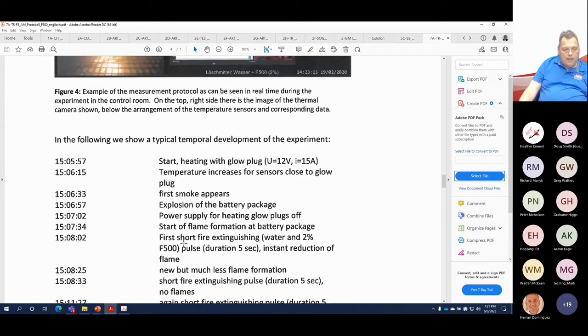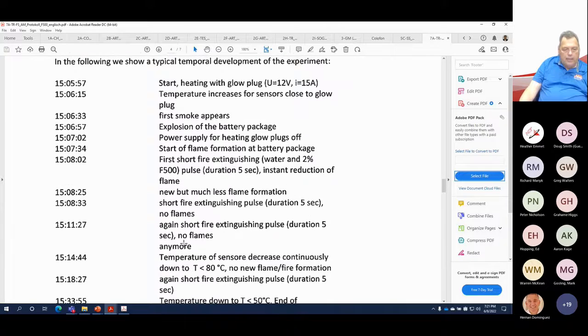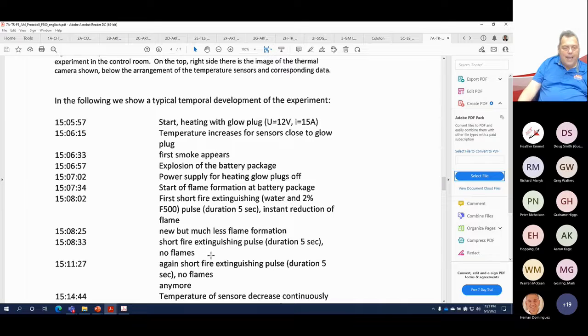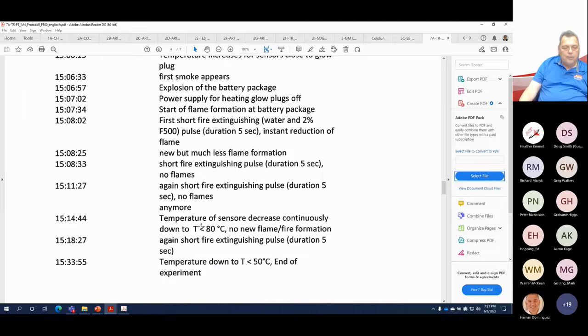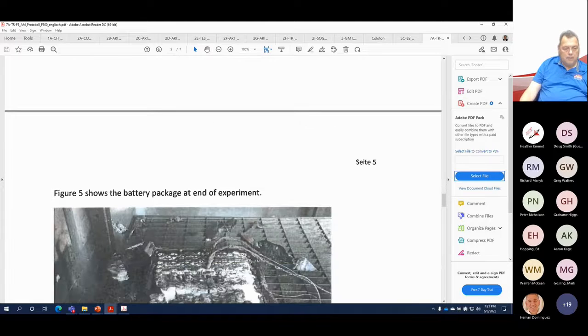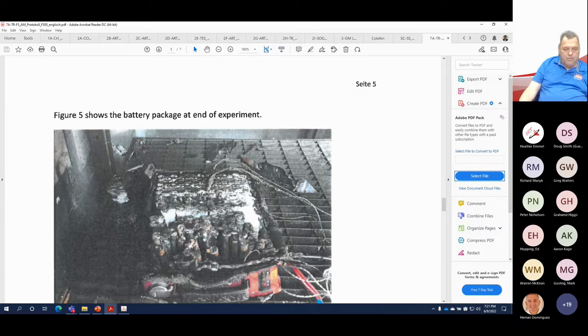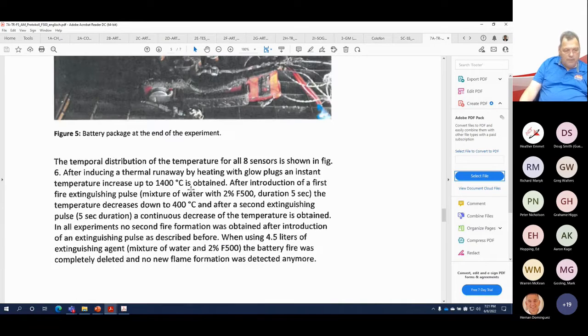So we have gone here from 1400 degrees down to less than 80, with only 3 5-second bursts of F500. And now we're waiting 15 minutes and the temperature is continuing to decline down to 50 C. Here we can see that we've stopped the thermal runaway and the fire propagation to other places.